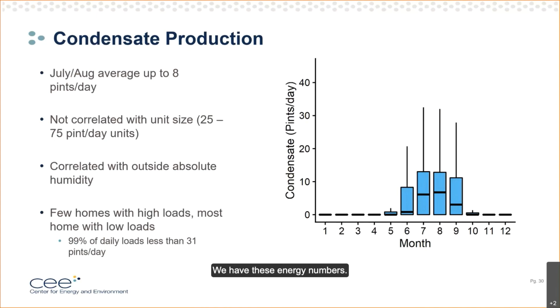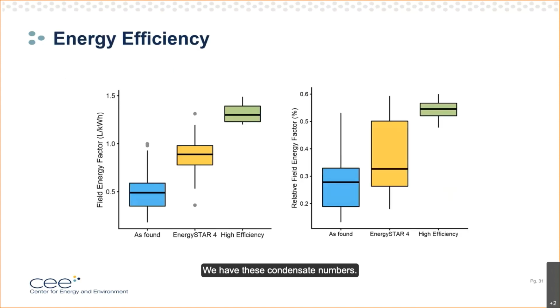So we have these energy numbers, we have these condensate numbers. This enables us to calculate energy efficiency, or the energy factor. We call this the field energy factor because, unlike the ratings, we calculate it over the range of conditions at each site. And the field energy factors we calculated for the study are shown here on the left. We've broken out as found, so all the units that we initially found. And then we looked individually at the ENERGY STAR 4 and the high efficiency groups of units.